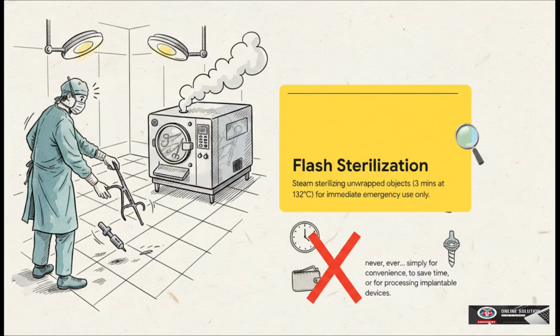But listen, as future medical leaders, you've got to enforce a strict rule here. This is solely for true emergencies. It is never, ever to be used just for convenience, to save time, or for processing implantable devices. Implants always require the full verified process.